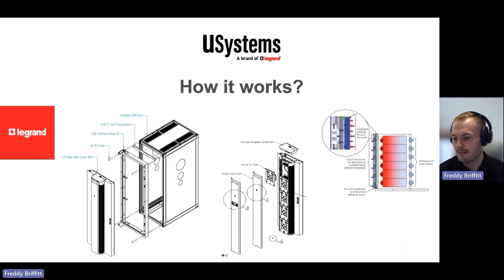So we pull the air, on most of the models of our rear door, over the coil. And then we have the management system - the CMS, cold logic management system, which monitors what's going on at the back of the rack, what's going on in the room, and then modulates the temperature depending on this.